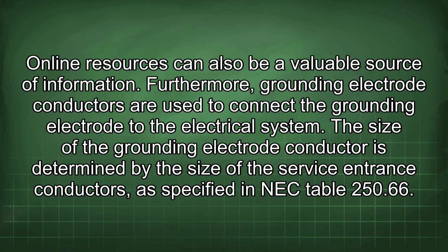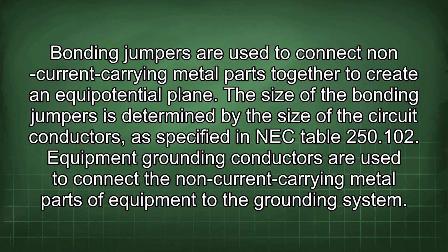Furthermore, grounding electrode conductors are used to connect the grounding electrode to the electrical system. The size of the grounding electrode conductor is determined by the size of the service entrance conductors, as specified in NEC Table 250.66. Bonding jumpers are used to connect non-current carrying metal parts together to create an equipotential plane. The size of the bonding jumpers is determined by the size of the circuit conductors, as specified in NEC Table 250.102.